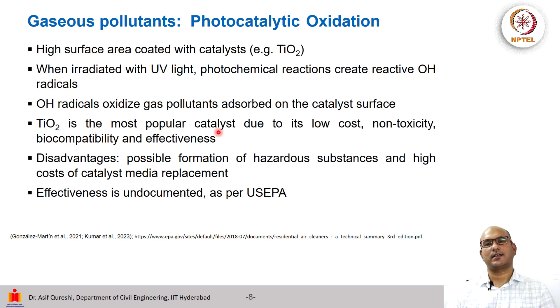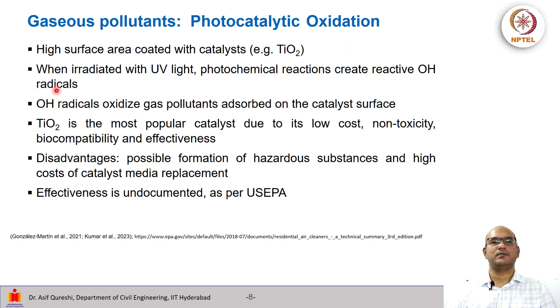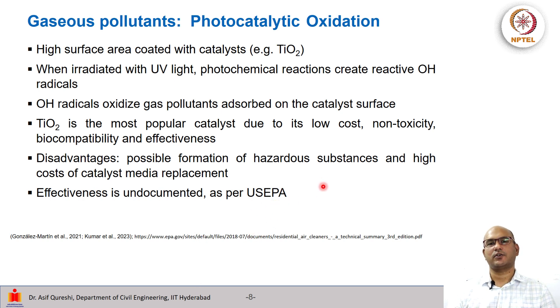TiO2 is the most popular catalyst due to its low cost, apparent low or non-toxicity, and compatibility and effectiveness. However, the issue with photocatalytic oxidation is the possible formation of hazardous substances, because OH radicals may react with available gaseous compounds and cause secondary aerosols or secondary pollutants. There is also a high cost of catalyst medium, and a US EPA document notes that the effectiveness of such methods is undocumented.